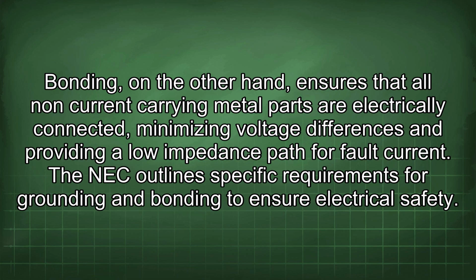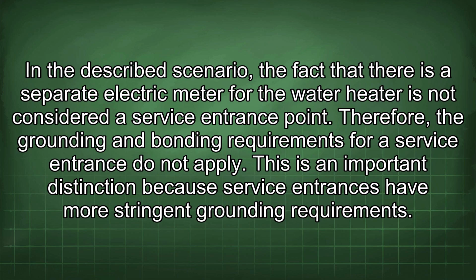The NEC outlines specific requirements for grounding and bonding to ensure electrical safety. In the described scenario, the fact that there is a separate electric meter for the water heater is not considered a service entrance point. Therefore, the grounding and bonding requirements for a service entrance do not apply. This is an important distinction because service entrances have more stringent grounding requirements.